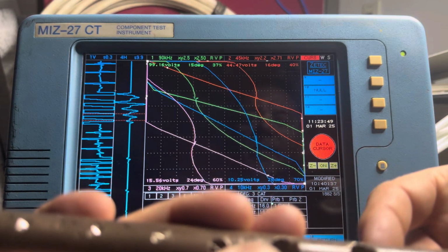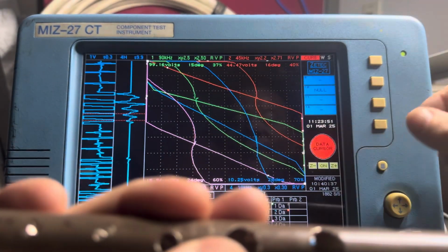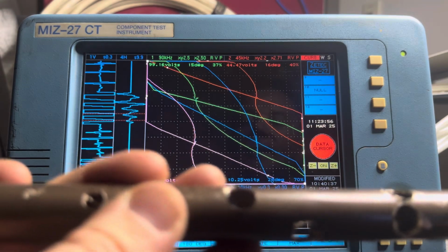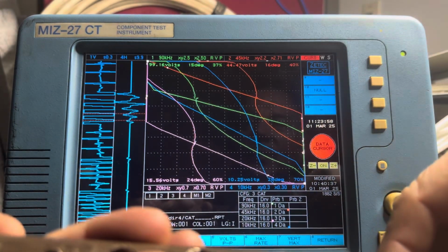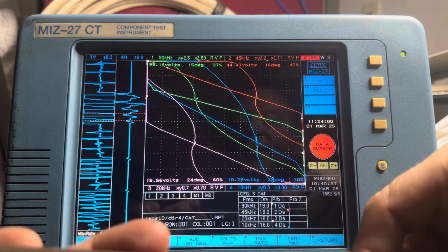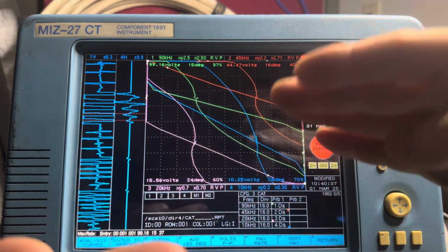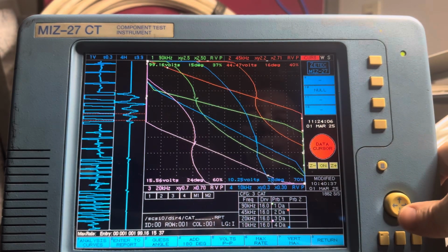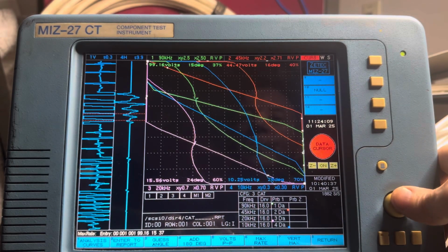See the larger diameter hole drop the phase even more. It's still rotating up towards that smaller diameter 100% or the 0.052 hole, but the phase of each individual channel is dropping down more towards probe wobble. So 15, 16, 24, 28.